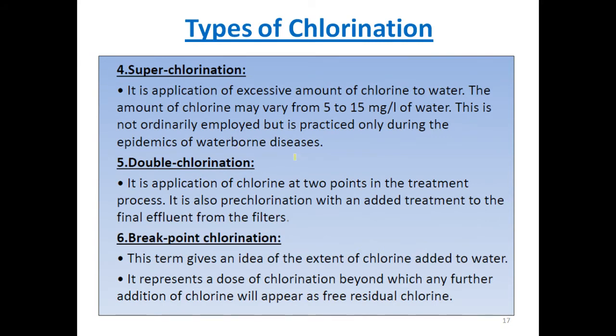The huge quantity of chlorine added in super-chlorination is such as to give about 1 to 2 mg per liter of residual chlorine beyond the breakpoint in the treated water. Super-chlorination gives a strong odor and taste of chlorine in the treated water, which has to be removed. So the method adopted for removing the odor and taste after super-chlorination is dechlorination.